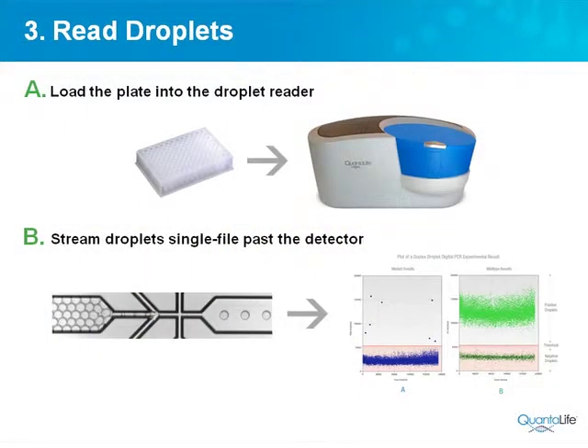We provide software for actually reading the droplets — the positives and negatives. The graph here shows droplets through time: droplet one through droplet 20,000. For every droplet we plot the fluorescence on the y-axis. The negative droplets have low fluorescence just from the poorly quenched probes, and these other droplets are the ones that have amplification in them, meaning the PCR reaction happened and there was a target present.